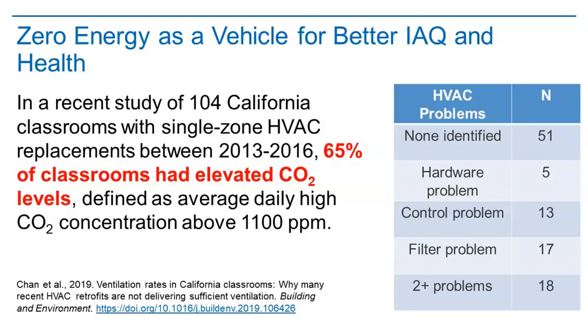They led a field team that inspected the HVAC equipment and identified issues like inadequate equipment or improper installation, controls not properly set so fans weren't operating at the right time, filter issues, and a whole range of other problems. Again, this was 65% of the buildings with recently renovated HVAC systems having elevated CO2 levels.